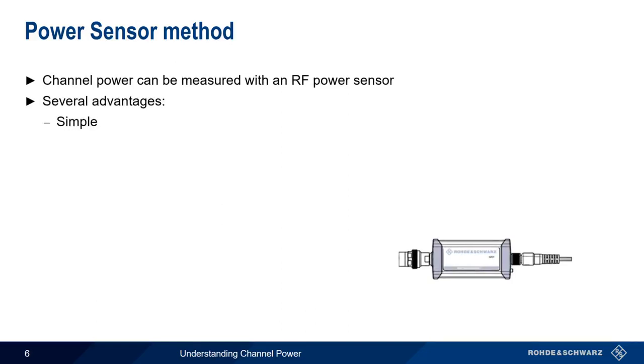It's a very simple measurement. Power sensors are relatively inexpensive, and they're also portable, which is important because this measurement is often made in the field. Depending on your power sensor, it also yields very accurate results.